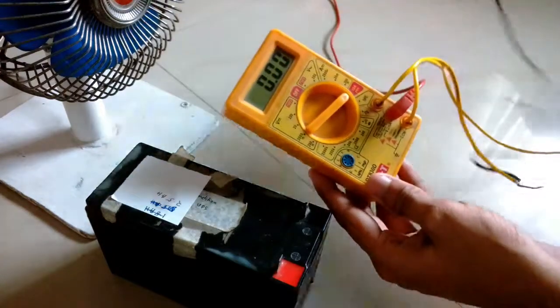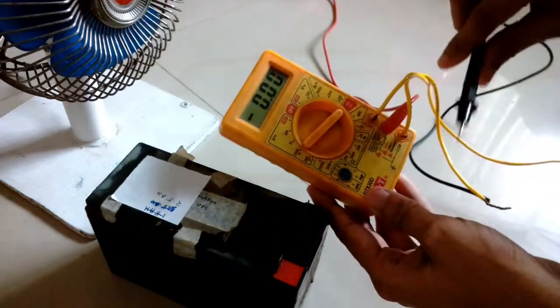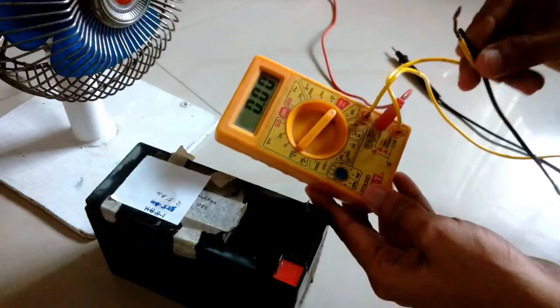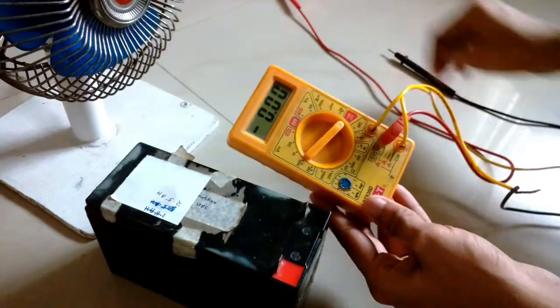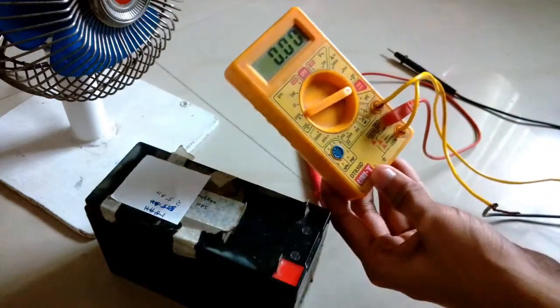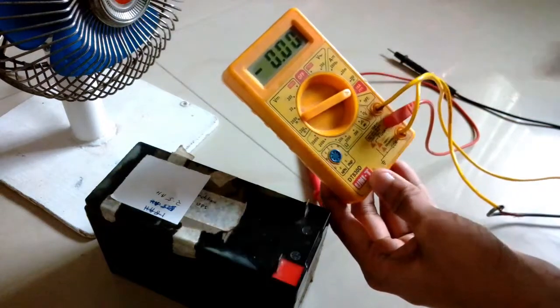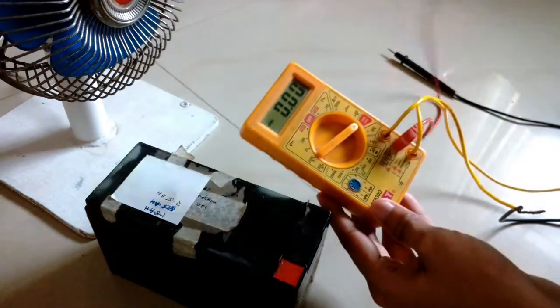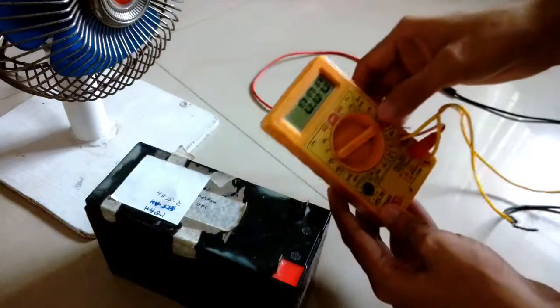In today's episode, I'm going to show you how you can measure more than 10 amps, such as 20 amp, 50 amp, or 100 amp continuously with these cheap multimeters. These multimeters can measure up to 10 amps unfused for 10 seconds, as written on the meter, and that's the maximum capacity of this meter.